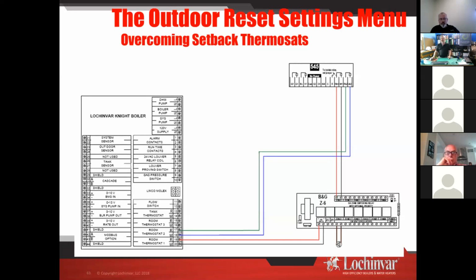And it doesn't always have to be higher. So if I set this for, I'm going to say 160, okay? And my first call here was looking for 130. I'm going to get that 30 degree bump in temperature until I get close enough that my second stage drops out. If I'm cold enough that this is looking for 170 or 180, a temperature above it, it'll default to that temperature, the higher temperature. So it doesn't always have to be the higher temperature, but just be the one that you want to use to boost it up. So it's a feature that's there.